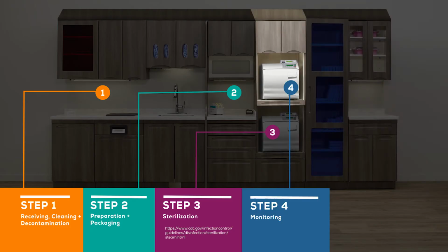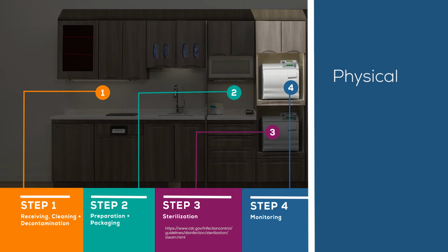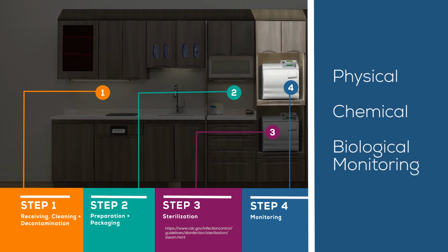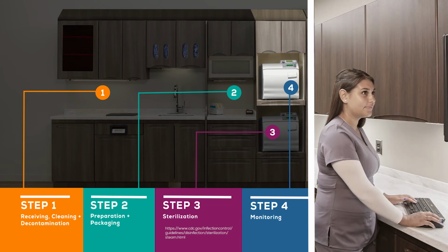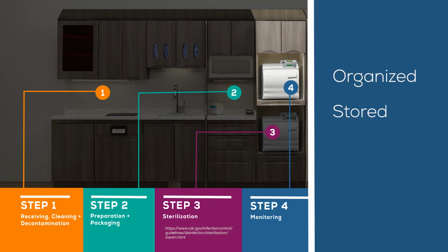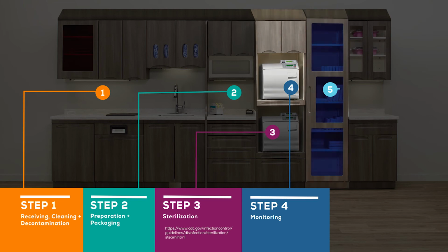Step 4. Monitoring. Use physical, chemical, and biological monitoring as required by local, state, and federal regulations to ensure the effectiveness of the sterilization process. Records of physical, chemical, and biological indicators of sterilizer performance should also be documented by either print or electronic means. These records must be organized, stored, and be accessible for a certain period of time as required by local, state, and federal regulations.